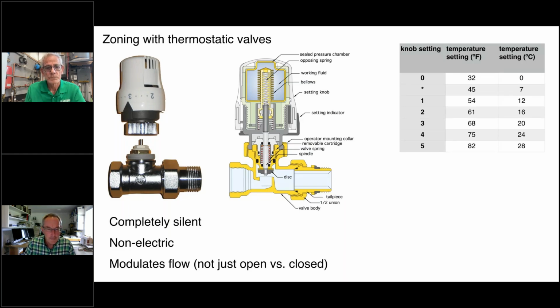Here's a cutaway. And real quickly, there is a bellows assembly that has a fluid in it. And that fluid expands and contracts in response to the temperature around this portion of the operator. So as it warms up, it's actually going to push down on the valve shaft, and that's going to reduce the flow going through there, and vice versa. As the room cools off, that bellows is going to allow that shaft to come back up again.